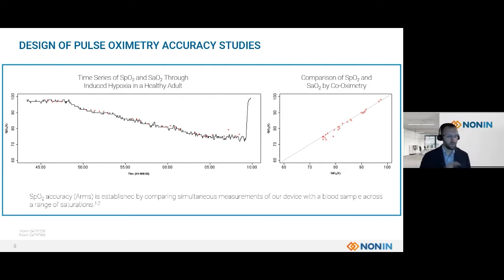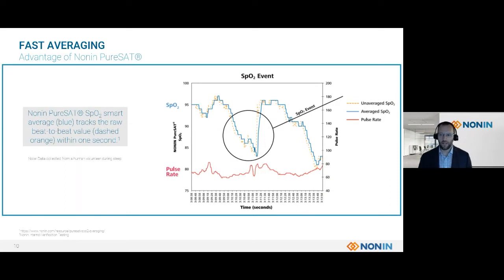So this is an artificial example, but let's look at a real example, and let's look at Nonin's averaging. Nonin's PureSAT technology uses an intelligent pulse-by-pulse averaging algorithm, and that is able to adjust for the patient's condition. PureSAT technology averaging automatically adjusts to the fastest response time that it can, of 3 seconds or faster, and there's no need to set a mode or setting in your system. In the example shown on the right-hand side, you can see the difference between a completely unaveraged SpO2, which is the dotted yellow line, and our PureSAT technology, which is the averaged SpO2.